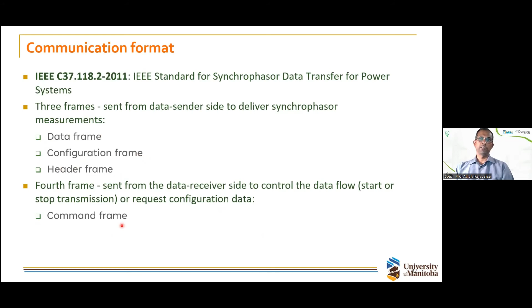Usually the PMU is like a server and the PDC is a client. So the PDC sends a command frame asking to send a configuration frame. Then the PMU sends back the configuration frame, and then the PDC knows what this PMU is going to send back.